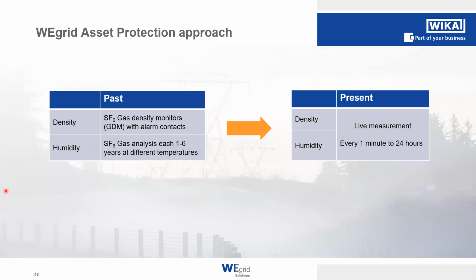In the present, we are moving to the live measurement. That means we are providing a system with sensors utilized that is measuring density, humidity, and also pressure and temperature every minute to every 24 hours. So this is a very live measurement, and we call this our move from a reactive-based maintenance to a condition-based maintenance strategy.